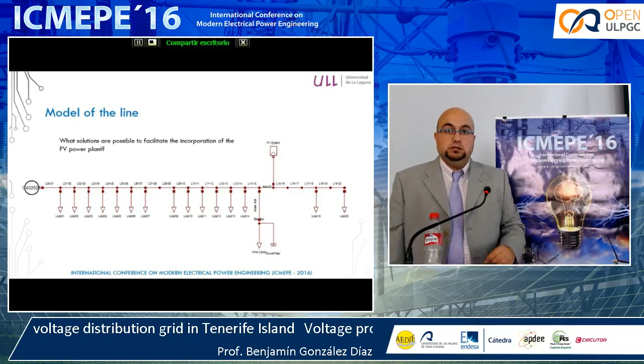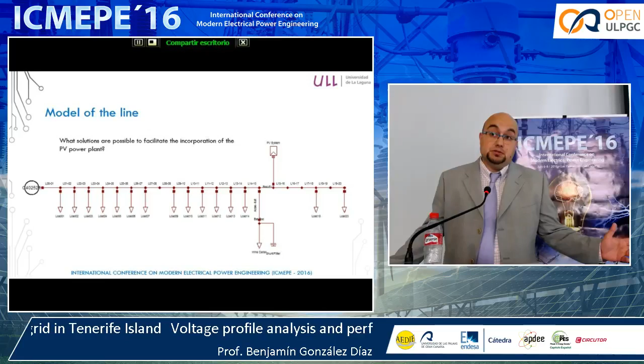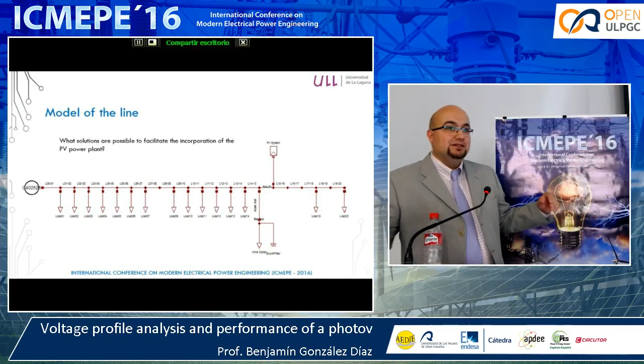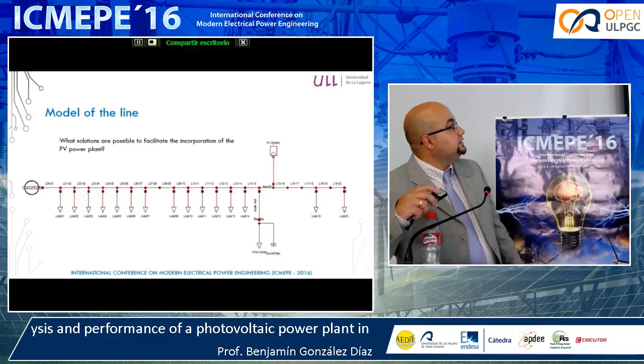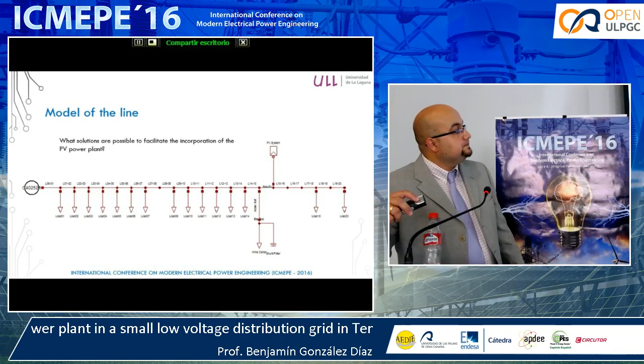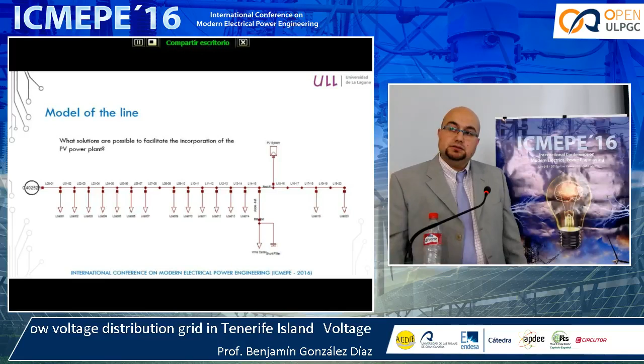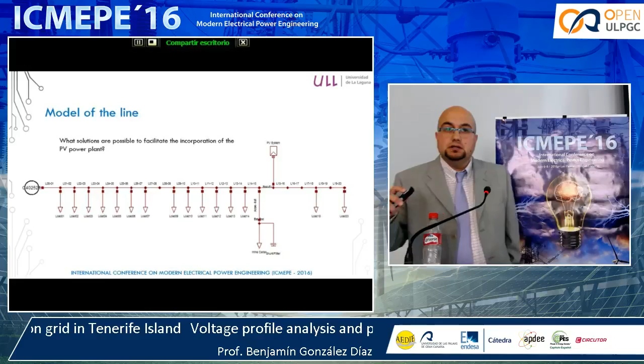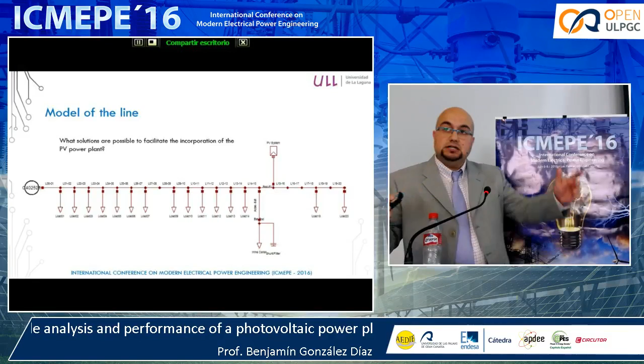What can we do? Well, the thing that we are able to do is model the line and try to fix what the problems are. So after a lot of measurements, this is more or less the profile of the line. This is the transformer. We have the loads of the customer here. We have the wine cellar here with the shunt filter. We have the PV power plant. And also we have 2 customers after the wine cellar. Here there is a special point. From here to here there are more or less 940 meters.